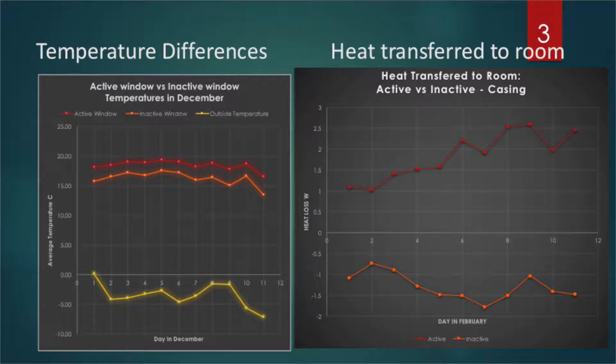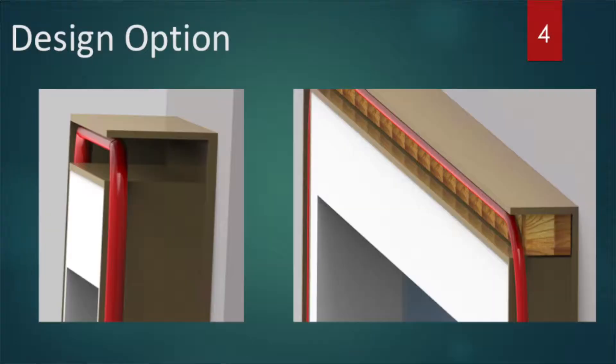There is a two percent temperature increase in the system. The next graph shows the heat transfer from the casing to the room only. The red curve shows the emitted heat to the room by the active window, and the orange curve shows the heat being lost by the inactive window.